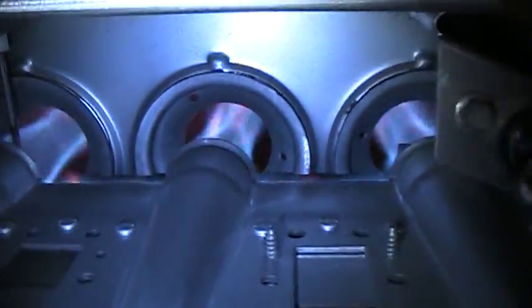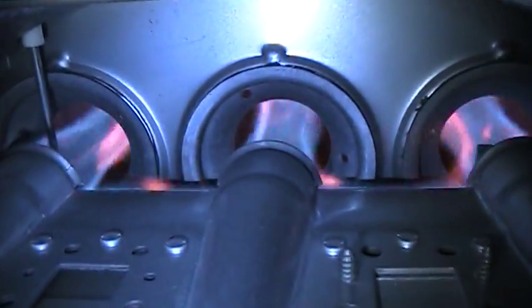There goes the blower. So basically, what it means is actually, I'm going to show you this one more time. The flames, you can definitely see there's quite a bit of orange on the flames. Basically, heat exchangers rust out. And when your heat exchanger rusts out, it cracks, and then those flames, they have CO, basically go into the blower chamber, and then the blower's blowing carbon monoxide all over your house. So that's why I have this here.